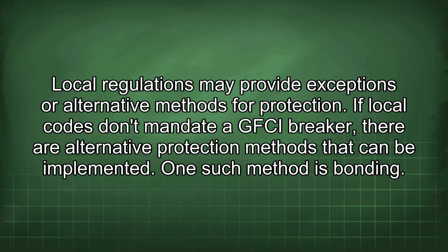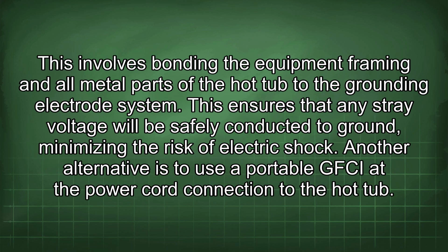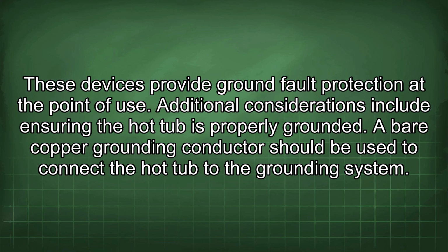One such method is bonding. This involves bonding the equipment framing and all metal parts of the hot tub to the grounding electrode system. This ensures that any stray voltage will be safely conducted to ground, minimizing the risk of electric shock. Another alternative is to use a portable GFCI at the power cord connection to the hot tub. These devices provide ground fault protection at the point of use.